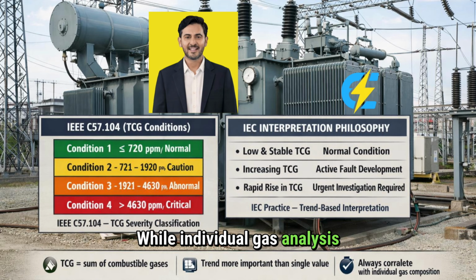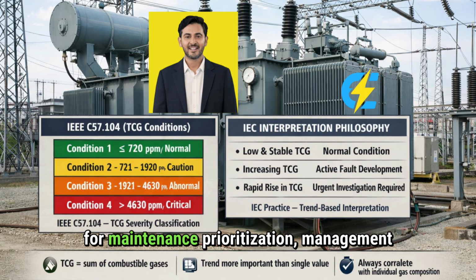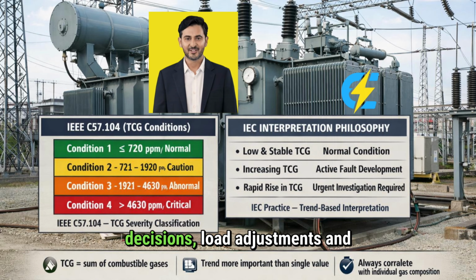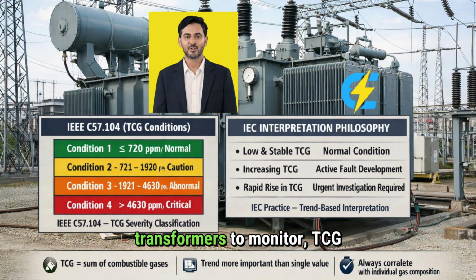While individual gas analysis requires you to consider multiple ratios, trends, and fault mechanisms, TCG gives you a single numerical view of overall fault activity inside your transformer. This makes it invaluable for maintenance prioritization, management decisions, load adjustments, and outage planning. When you have 50 transformers to monitor, TCG helps you focus on the ones that need immediate attention. IEEE C57.104 defines 4 distinct TCG condition levels, and understanding these is crucial for any engineer working with transformers.